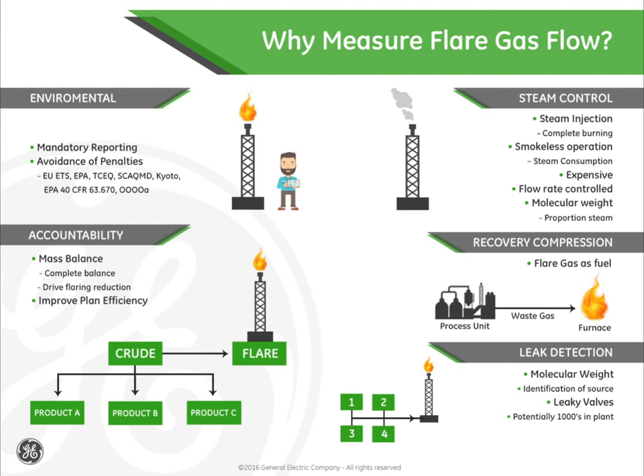Since the GF-868 meter can also measure molecular weight, it can help pinpoint process leaks quickly, acting as an inline diagnostic tool to improve process reliability. In a flare gas recovery system, the GF-868 meter can measure mass flow of the flare gas for further processing. The molecular weight feature on the GF-868 can even aid in steam control for your flare by using the GE patented methodology for inert gas compensation.